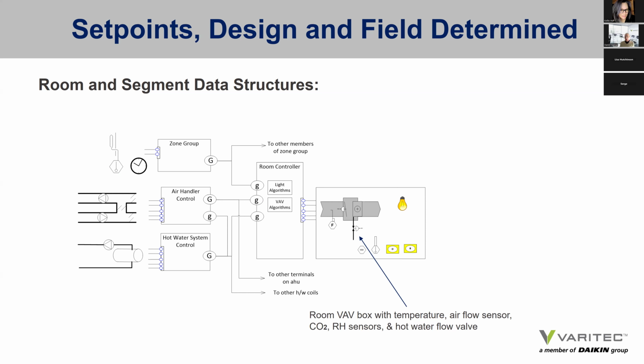It also is reading relative humidity potentially in the room. It also has a controller that will regulate a hot water valve to supply reheat to the VAV box during our cooler, shoulder seasons of the year, and also can actually regulate airflow based on carbon dioxide concentrations. Then that VAV box is hardwired to the room VAV box controller, which is also hardwired to the water valve as well. And it's from that controller that the various VAV algorithms are written.